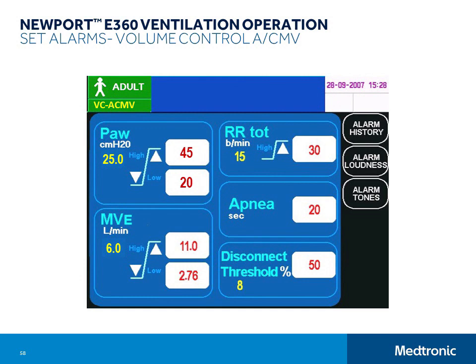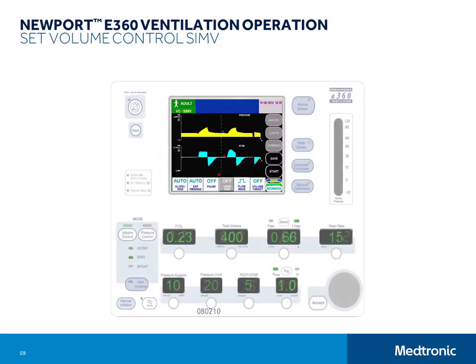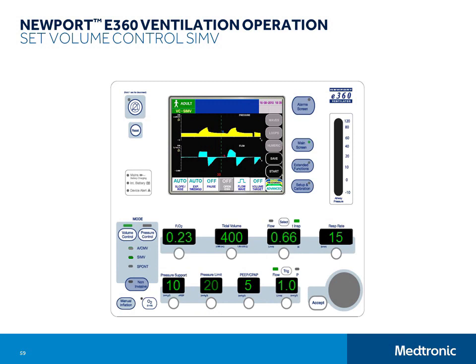Okay, now if you want to change from volume control ACMV to volume control SIMV, just press the volume control button until volume control SIMV is lit, then press accept. In addition to the mandatory breath settings, you will need to set spontaneous breath settings. The pressure support control determines how spontaneous breaths are supported. Set the pressure support control to deliver the desired level of support above PEEP. And then set slope rise and expiratory threshold on the GUI screen. Remember that those of you with P, E, and T models can set these two parameters to auto so that e360's intelligent control system will manage them for you breath by breath. Remember to check and, if necessary, change the alarm settings whenever you change ventilation parameter settings.